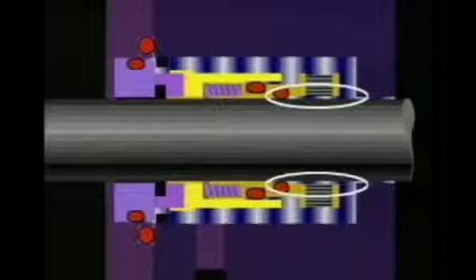Now, the seal design is complete. An assembly that stops leakage in three critical areas: at the seal faces, at the face of the stuffing box, and under the seal along the shaft.